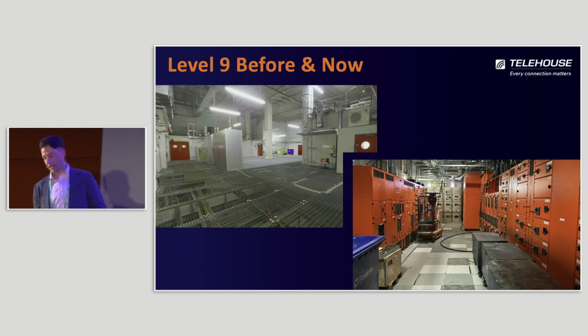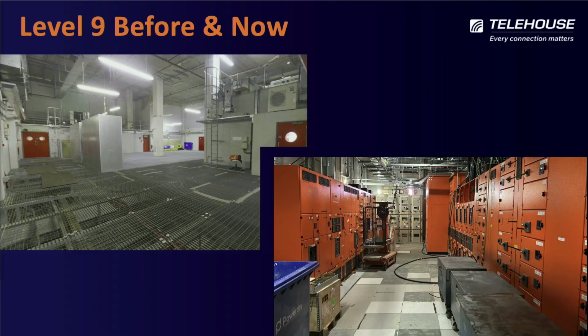Level 9: looking at all aspects of the building, the mechanical plant wasn't UPS-backed—it didn't have uninterrupted power supply, just generator supply. So we've repurposed the old generator room on level 9 into new UPS rooms to support our mechanical equipment on the roof and upper levels.